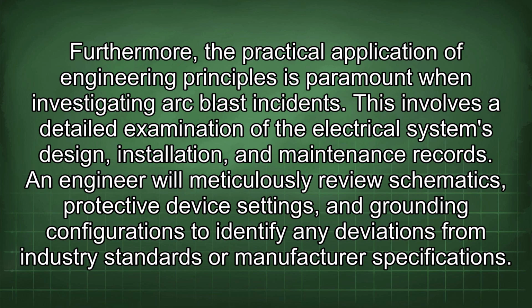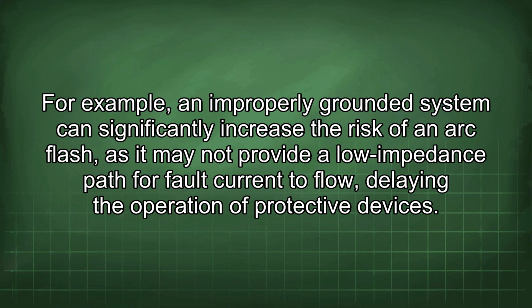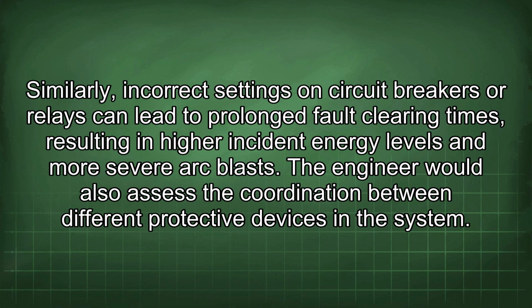Furthermore, the practical application of engineering principles is paramount when investigating arc blast incidents. This involves a detailed examination of the electrical system's design, installation, and maintenance records. An engineer will meticulously review schematics, protective device settings, and grounding configurations to identify any deviations from industry standards or manufacturer specifications. For example, an improperly grounded system can significantly increase the risk of an arc flash, as it may not provide a low impedance path for fault current to flow, delaying the operation of protective devices. Similarly, incorrect settings on circuit breakers or relays can lead to prolonged fault clearing times, resulting in higher incident energy levels and more severe arc blasts.